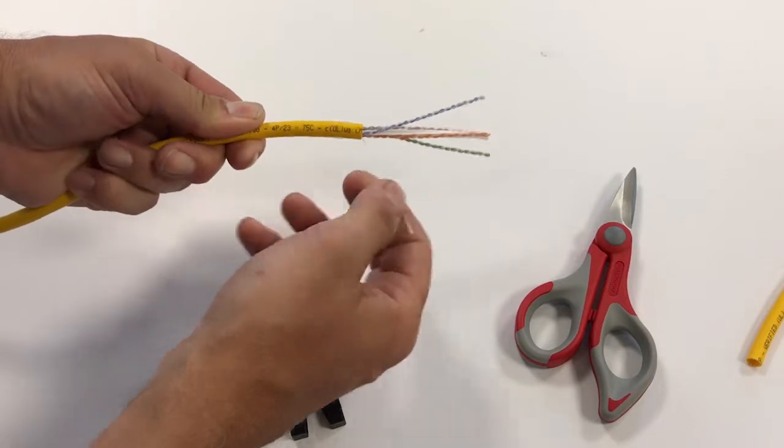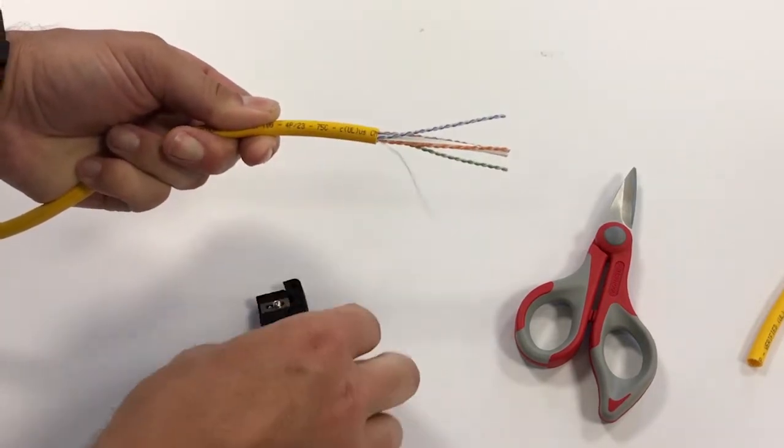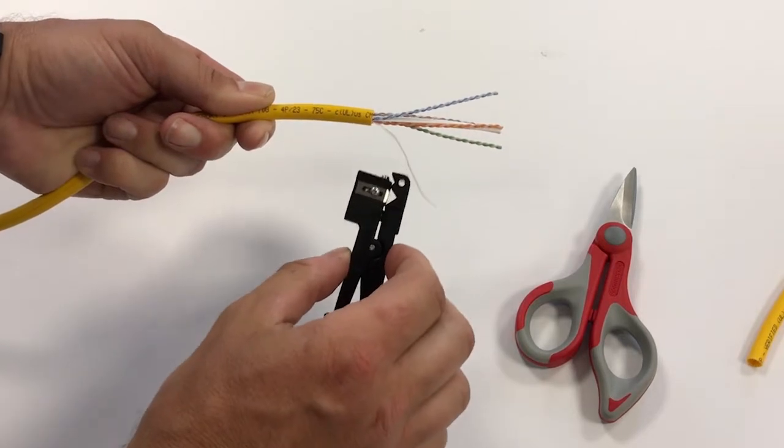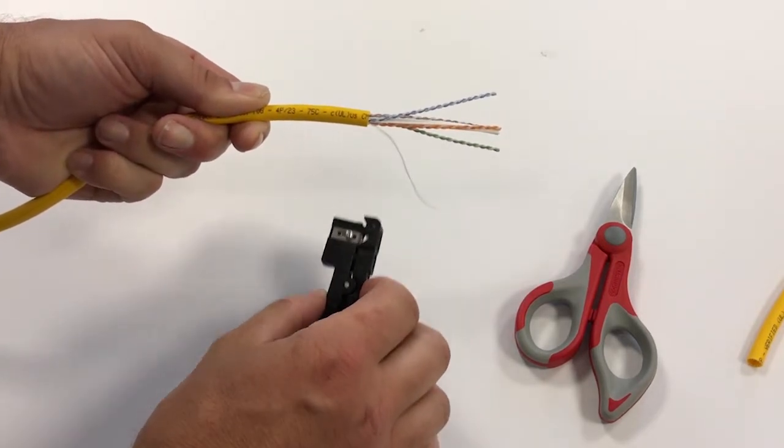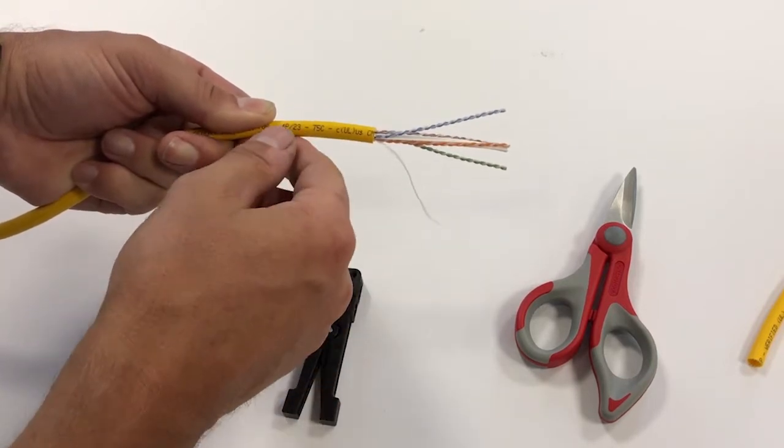The purpose of the ripcord is to allow you to pull it back and expose core that hasn't potentially been nicked by the cable ringer. Sometimes the cable ringer blade can cut into the insulation and the copper, and that can negatively impact performance.